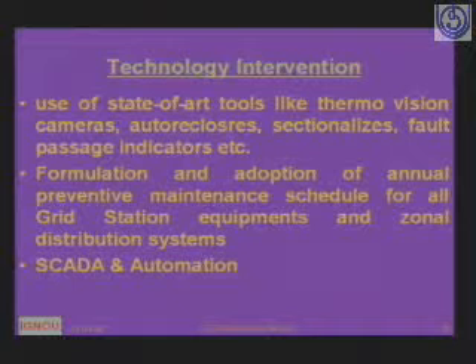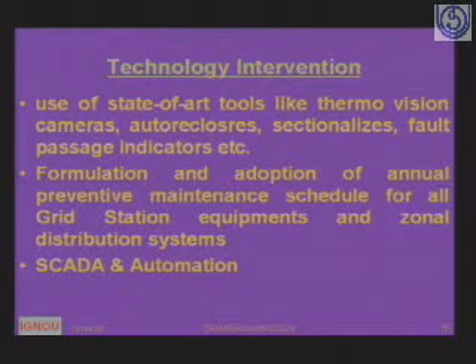What are the technological interventions? Thermovision cameras - those around Delhi or in the northern region have seen successive blackouts because of hotspots in insulators. Now thermovision cameras can detect these hotspots. If we periodically check connections, terminations, and insulators for cracking or chipping, or during early hours when mist combines with dust to form a plaster, that plaster is a very good conductor of electricity. Along the insulator there is tracking of electricity that short circuits the connections. So thermovision cameras are used in power plant switch yards as well as along transmission networks.